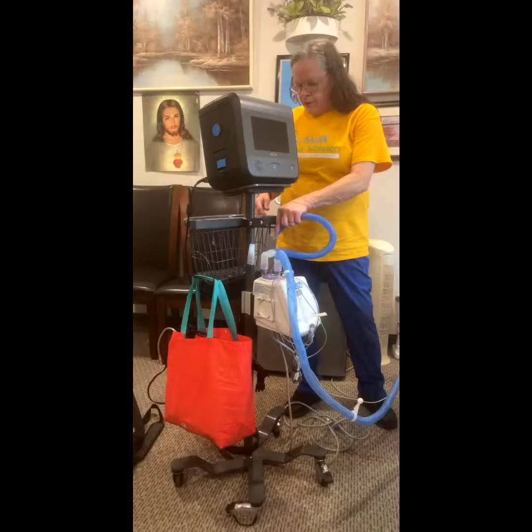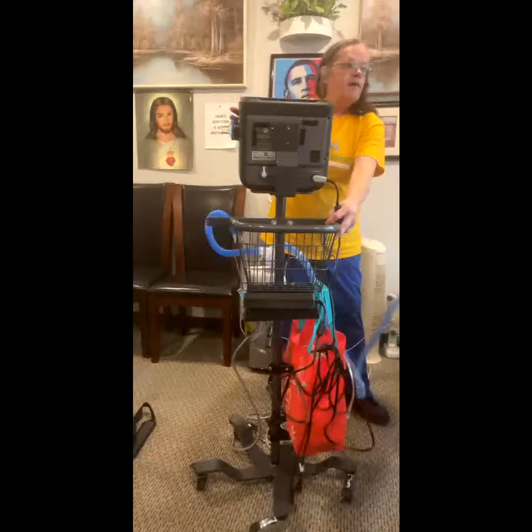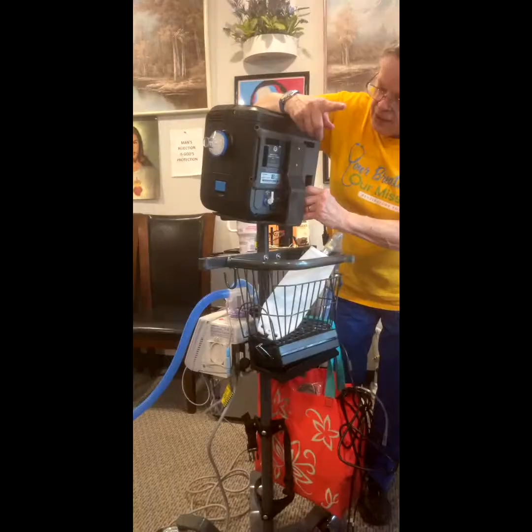One thing you need to know about this ventilator: there are 4 filters, literally 4 filters. You have your air filter and fan filter, similar to the LTV 1150 but slightly bigger. These get changed every 6 months but cleaned periodically. You don't want them getting really dusty because that can overheat the vent.